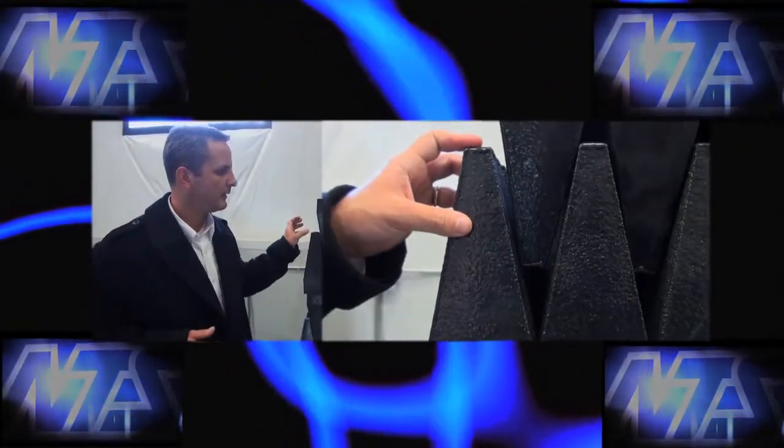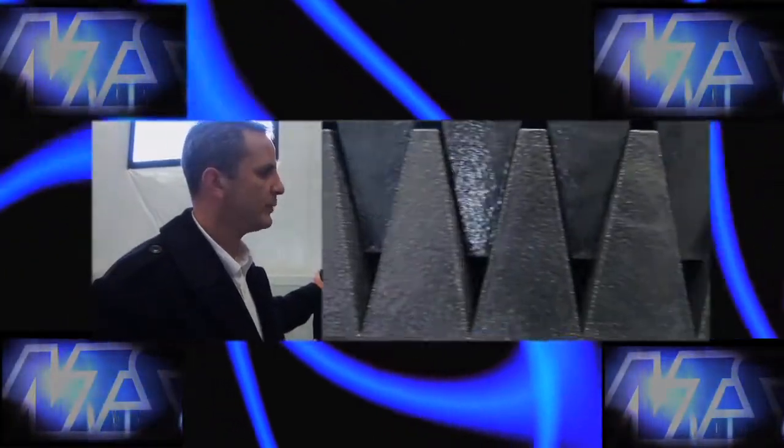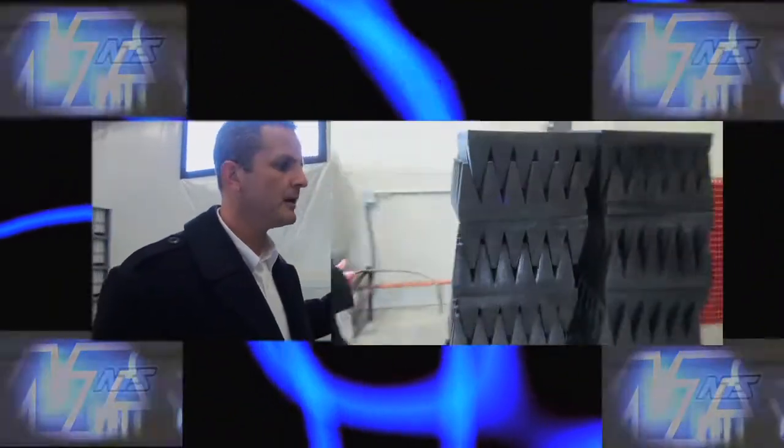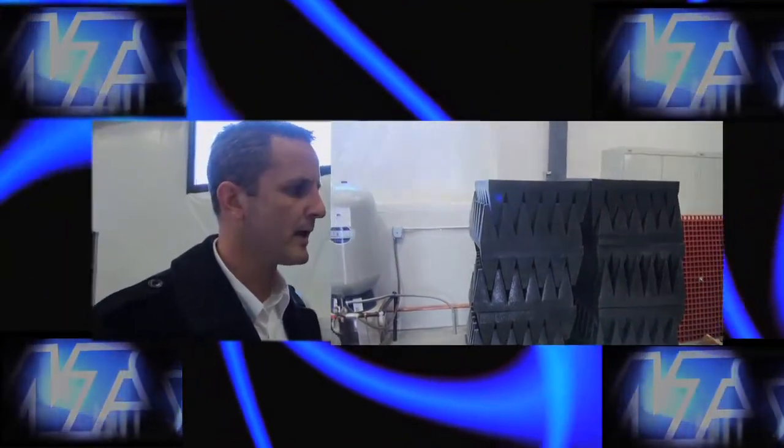These are part of a SVSWR kit that we bought from ETS Lindgren to layer the floor of the 10-meter chamber as well as the 3-meter chamber to meet our SVSWR requirement for 61000-4-3.